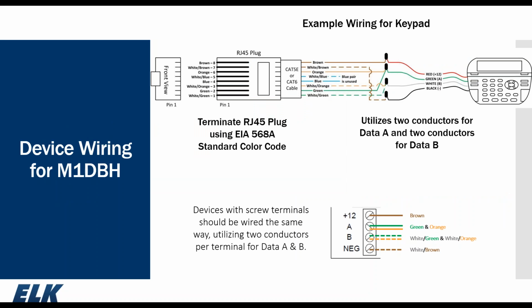This is what a typical wiring scenario would look like if you're using the M1 DBH out to, say, a keypad. We have our RJ45 connector. At the wiring harness on the keypads, you'll have 2 wires under data A. You have your orange and your green. The orange is data A. The green is the return path. For data B, we have white-orange for data B, and then the white-green is the return path for data B. For a device with screw terminals, you simply land your solid orange and solid green under data A. The data B would be your white-orange and white-green connection.